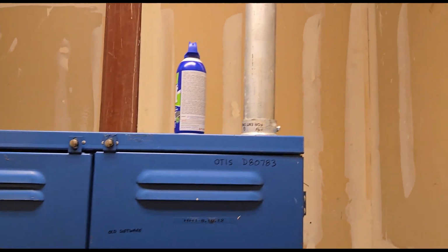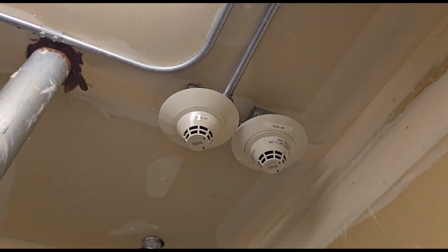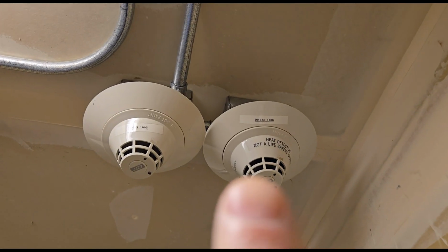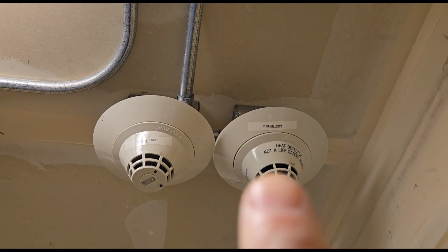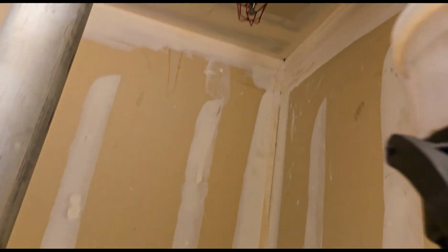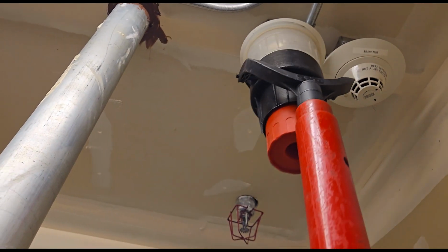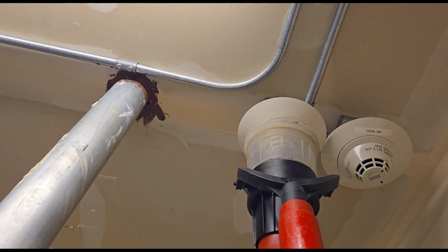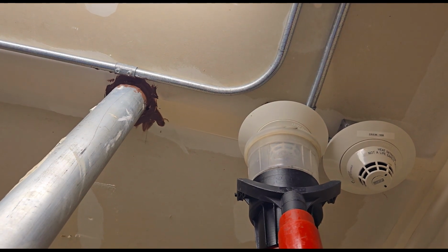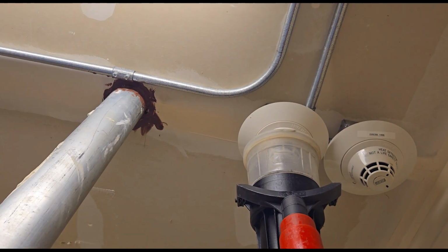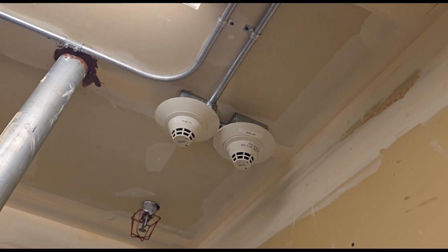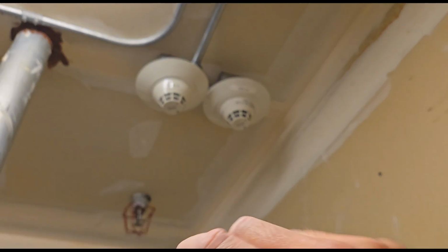All right, back in the elevator machine room. So now we're gonna do the machine room smoke and heat. So you got the smoke on your left and the heat on the right. The heat on the right has some lettering on it to let you know it's a heat detector. So just like before, gonna send our smoke, except this time it's in the machine room. Put a little puff in there. Get this to activate. Okay, it's active. And then we air it out.